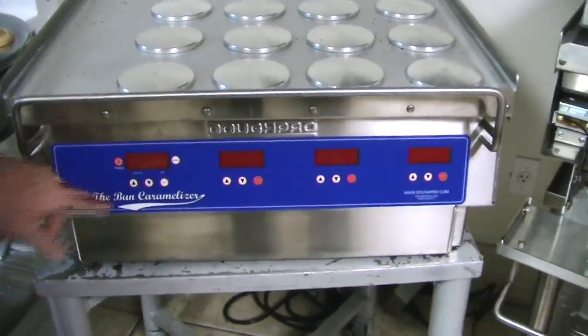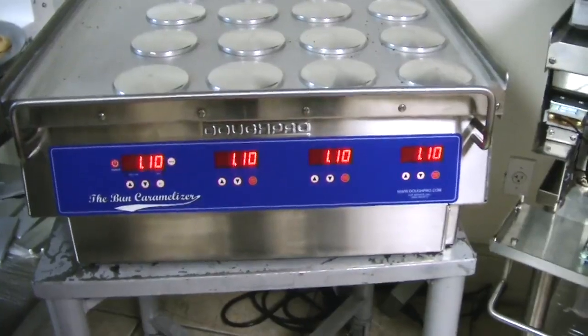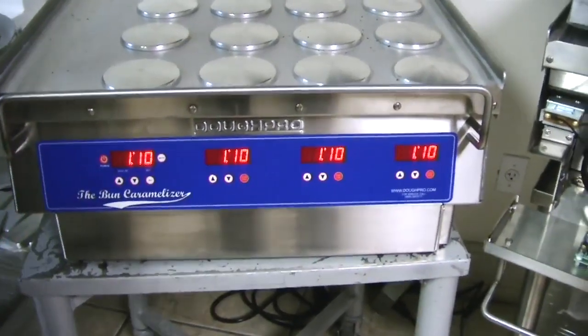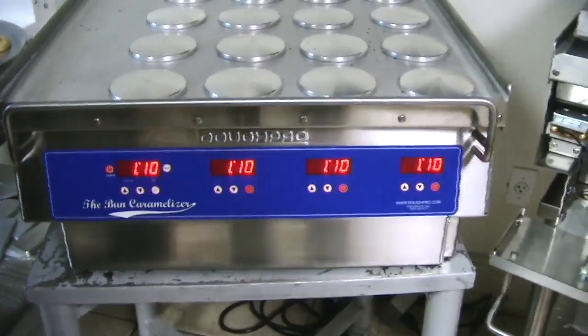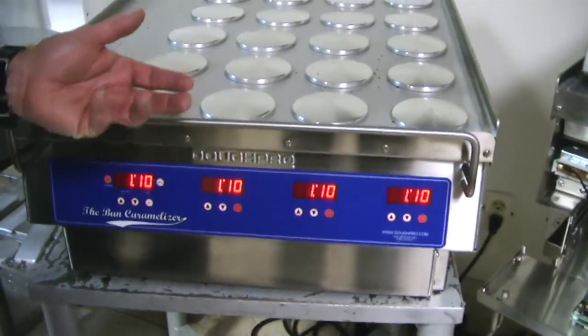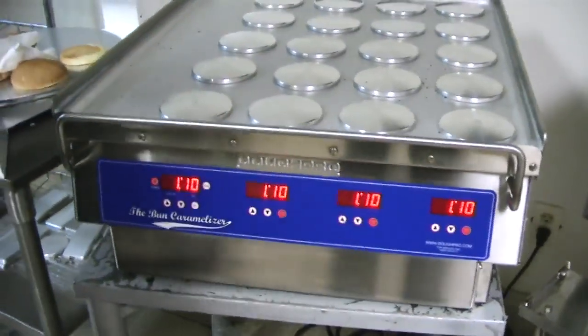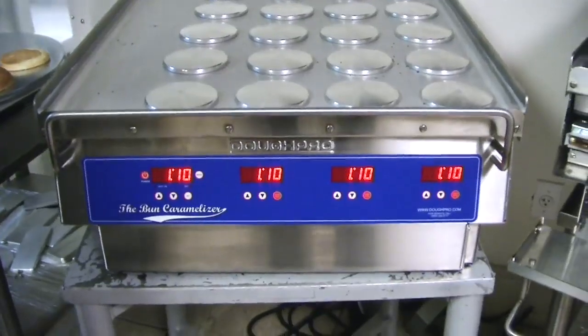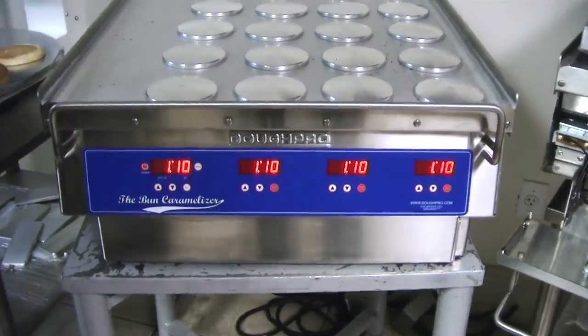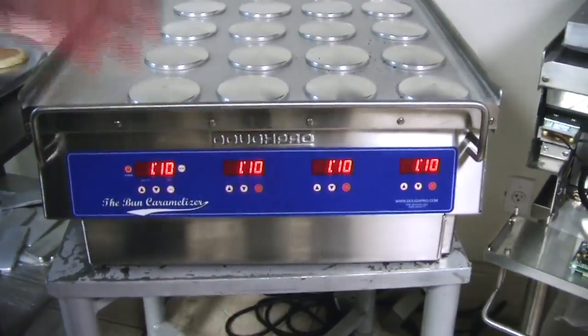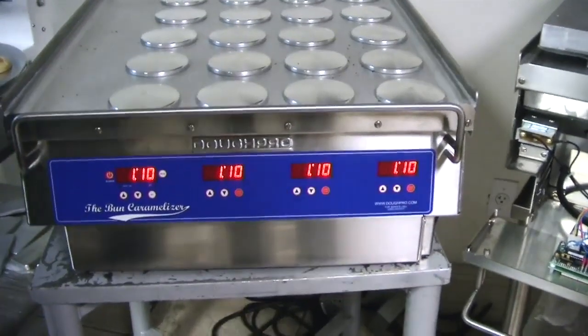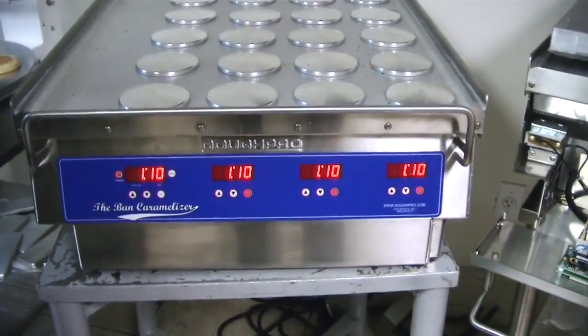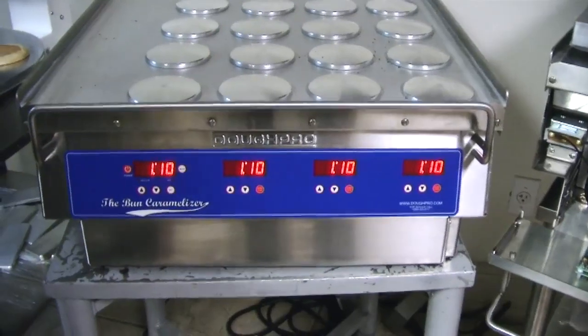If you turn this on and nothing happens, obviously the first thing to find out is whether it's plugged in. I know this sounds silly, but sometimes I've seen it where they go through all this technical stuff and find out it wasn't plugged in. Or if the main circuit breaker in the building threw, check to see if the circuit breaker needs to be reset or not.